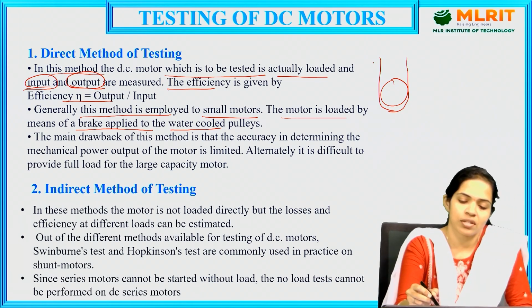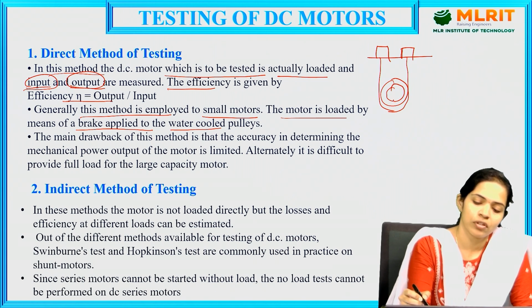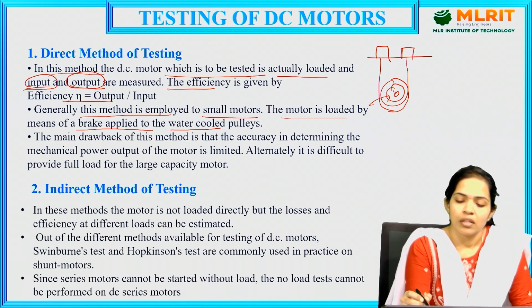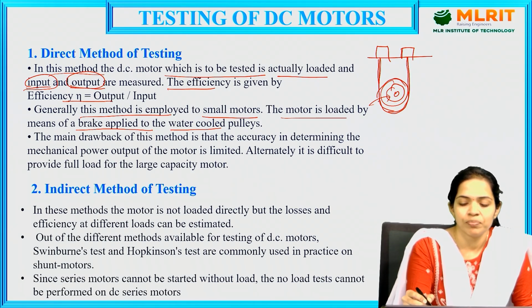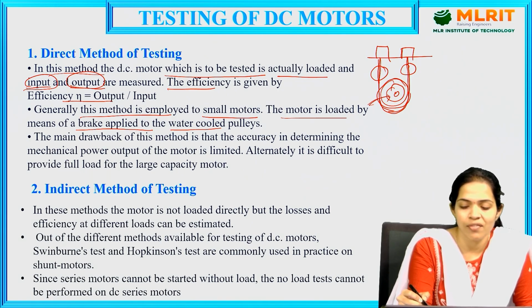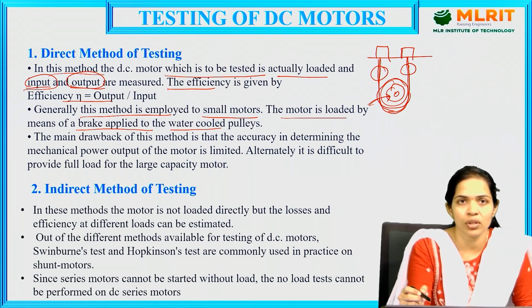drum which is given. This drum will have a provision for pouring water into it, so this is nothing but the pulley arrangement to add the loads on the motor drum. We have scales on this pulley arrangement to note down how much load is being applied on the motor, and we have a provision for water cooling here as well. After loading the motor to its rated conditions, we have to cool down the motor so that it can be operated for further applications or further increase in load.